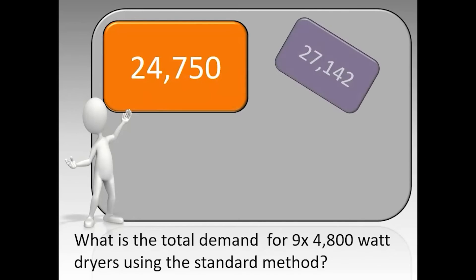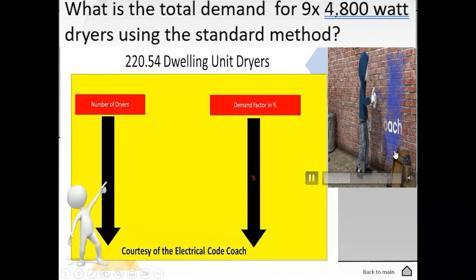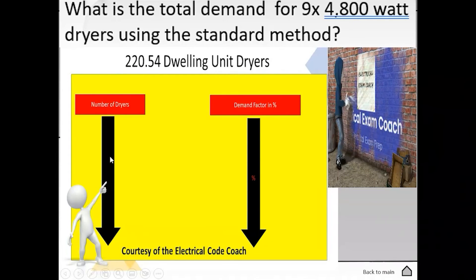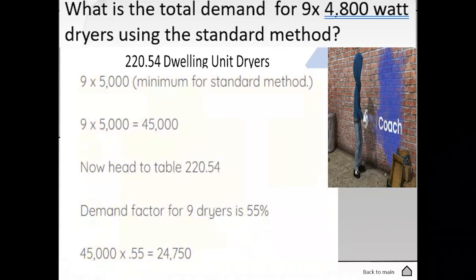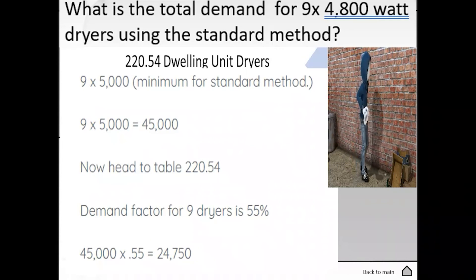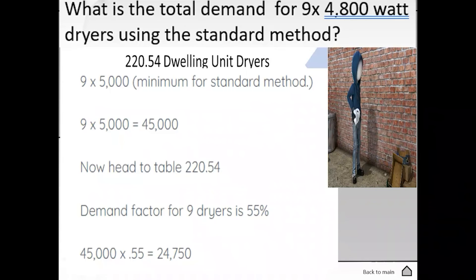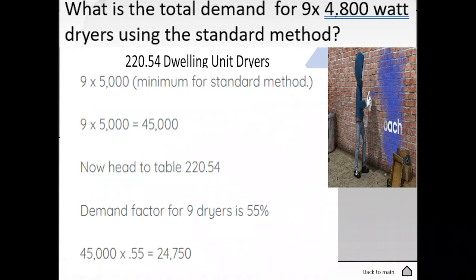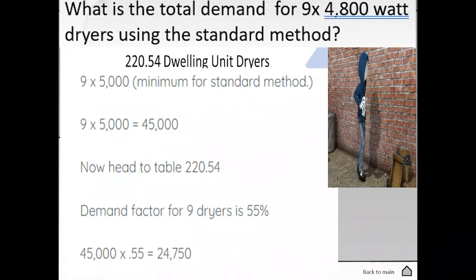What is the total demand for nine 4,800-watt dryers using the standard method? The correct answer is 24,750. We start by going to table 220.54, find our number of dryers on the left-hand side, and tee off with our demand factor. We take our nine dryers and multiply them by 5,000 — the minimum for the standard method, or the nameplate, whichever is greater. Nine multiplied by 5,000 equals 45,000. The demand factor is 55%. We multiply 45,000 by 0.55 and get 24,750.